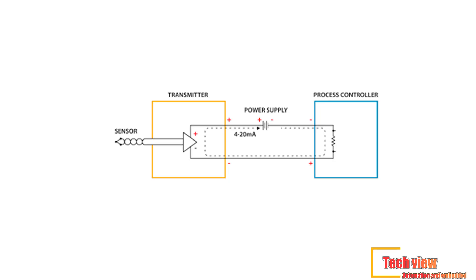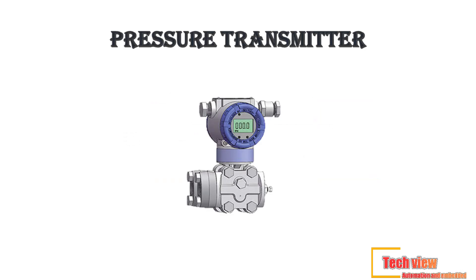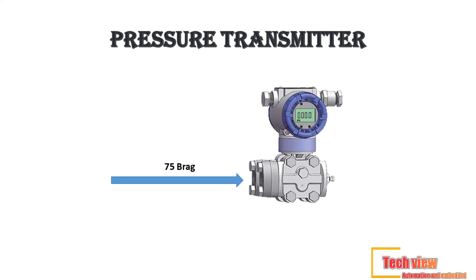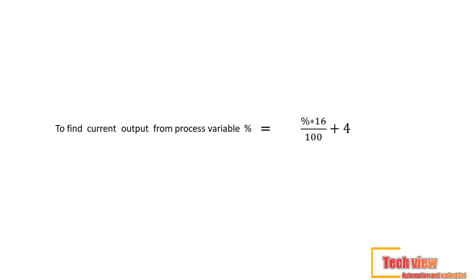First we will calculate the milliamps from the process variables. Before calculating milliamps, we have to convert our process variables to percentage. Let's assume we have a pressure transmitter whose calibration range is 0 to 200 bar. The transmitter is connected in the pipeline and currently measures 75 bar. We have to find the milliamps output from the transmitter. For that we use a formula: current output equals percentage of process variable times 16, divided by 100, plus 4.